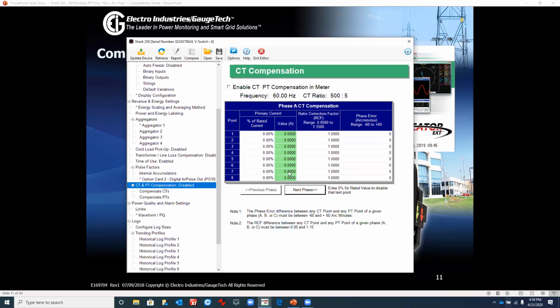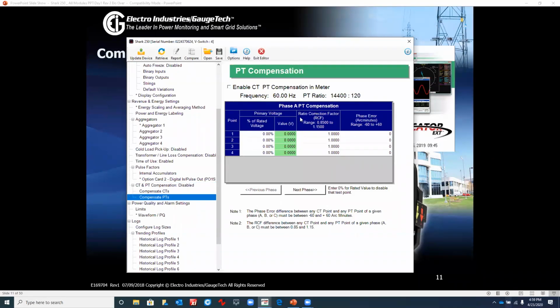As you can see, there are A, B, C CT compensation values, and that's for the CT, so you would enter those values in. For PTs, you would do something very similar. You get the values and you would enter those in for A, B, C phases.